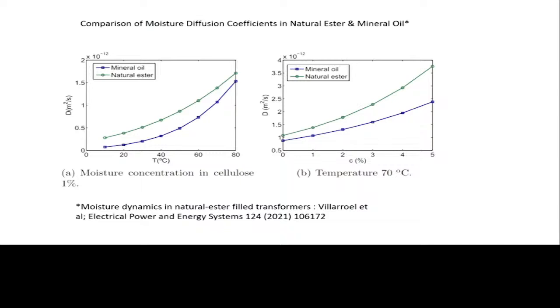Now, based on this, a lot of studies have been done on the moisture diffusion coefficients. Ultimately, everything has to be quantified. You cannot just go by saying, okay, I have got an oil which is absorbing moisture and it has got to behave better. No. You have to measure the moisture diffusion coefficients. This is an interesting paper where the moisture migration from paper to oil was measured. You can very clearly see here, the top line, that is green, is the natural ester, and the bottom one is for the mineral oil. So you can see that the diffusion coefficients for natural ester are very good. That is, the diffusion constants for natural ester are going to be much higher than for mineral oil. That is, from paper, the moisture is going to migrate much faster in the case of ester oil compared to mineral oil. That is what this slide shows.